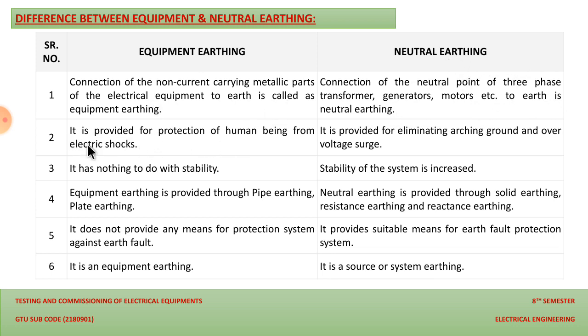Now it is provided for the protection of human beings from electric shock, and this is provided for eliminating the arcing ground. Means whenever a fault occurs in such a large system, a large arc is generated, and losses of charges will take place. So yes, we can protect this system with the help of neutral earthing and over voltage surges.